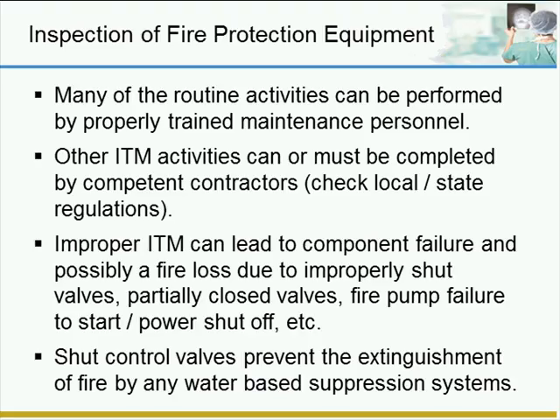Again, we see the importance of inspection, testing, and maintenance of sprinkler systems. Draw your attention to bullet three, where improper inspection, testing, and maintenance can lead to component failure and possibly a fire due to an improperly shut valve or partially closed valves, pump failure, failure to start, or power shutdown concerning the fire pump. And finally, shut valves prevent the extinguishment of fire by any water-based suppression systems. This is known as an impairment, and whenever sprinkler valves are shut for more than 4 hours, you should notify both the fire department and your insurance carrier. This is typically for large-scale maintenance on the system.